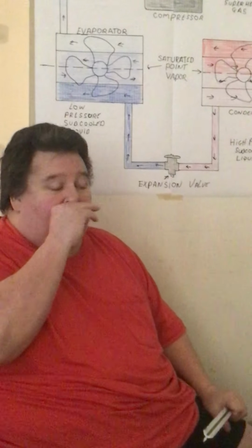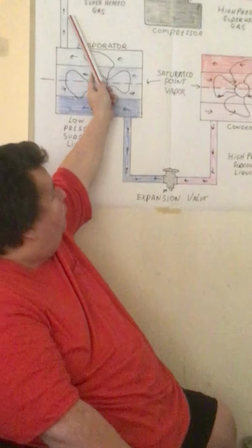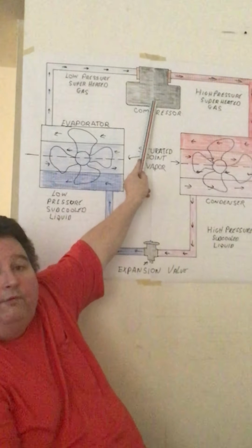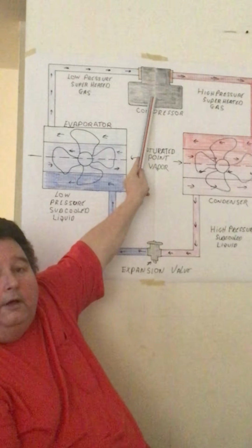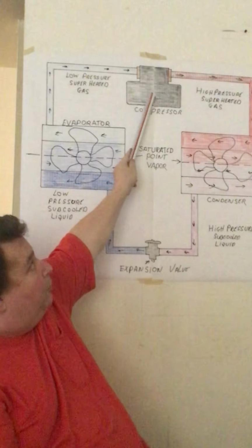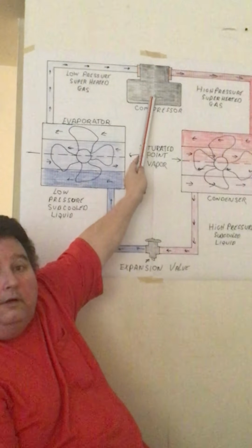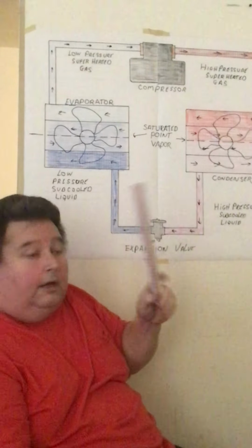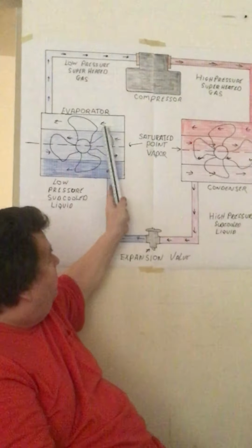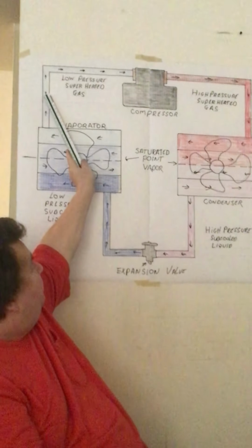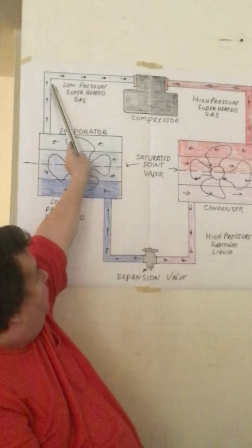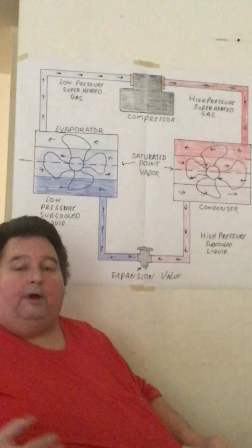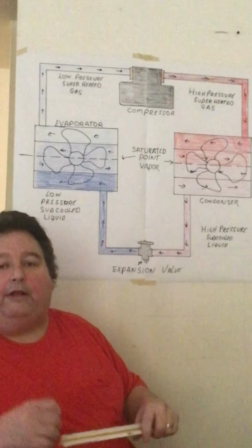And when you have too much superheat, the compressor is going to overheat because you're not getting enough refrigerant back, because the refrigerant is actually what cools the compressor down. If you have too little superheat, you have too much liquid, and maybe the liquid will be up to here instead of vapor. It's going to come in, liquid is going to go into the compressor, and that's called slugging, and that's no good.